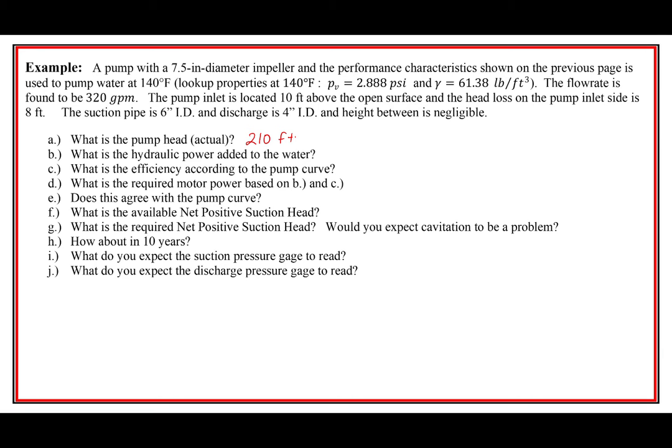what we ended up with was 311, is that right? No, 303, right? So we had 303, but this is going to be the H_p, so I'll write it out, it's H_p actual, 210 feet, where H_i was 303 according to our velocity triangles, 303.1 feet. So interesting. Let's go ahead and take a ratio. 210 divided by 303.1 is 69.28%.